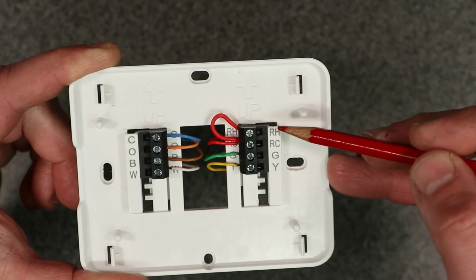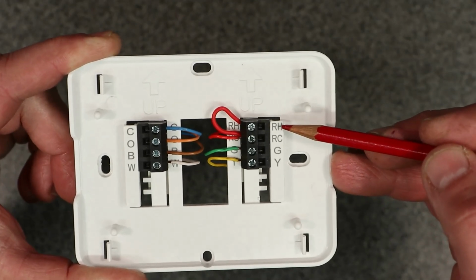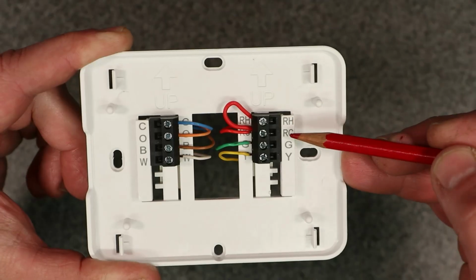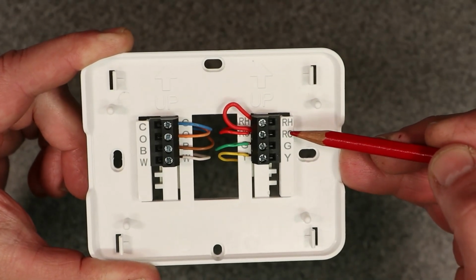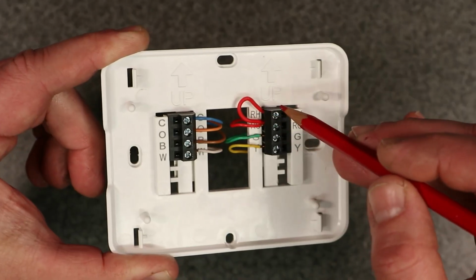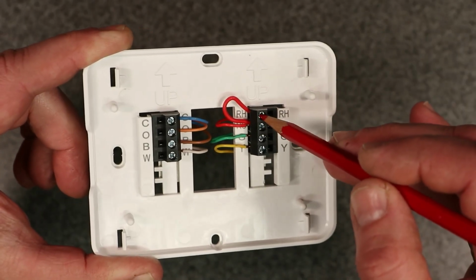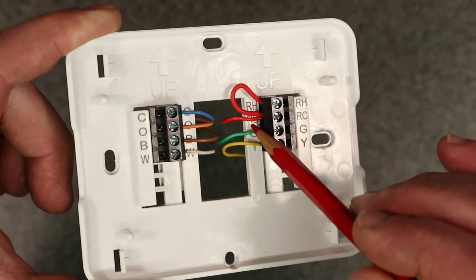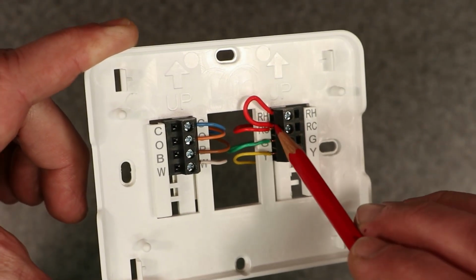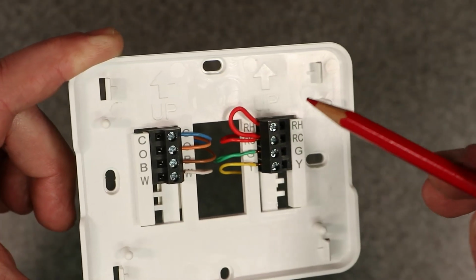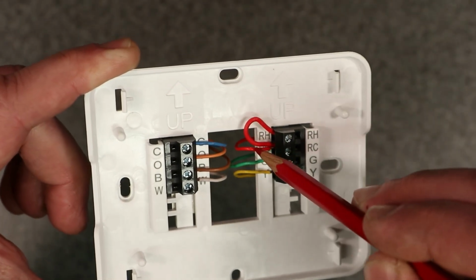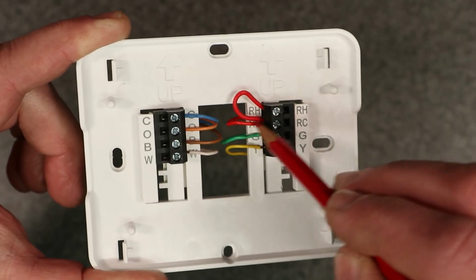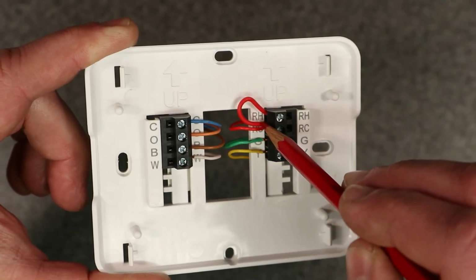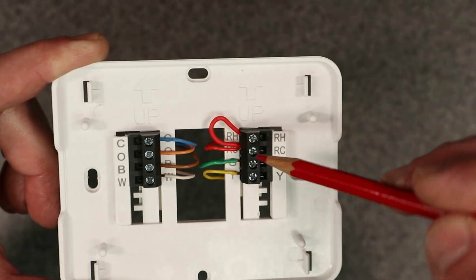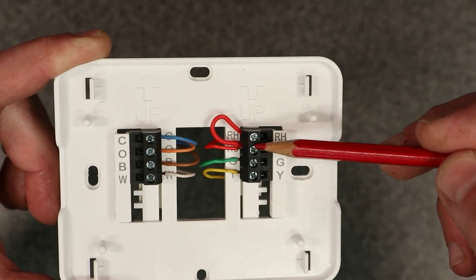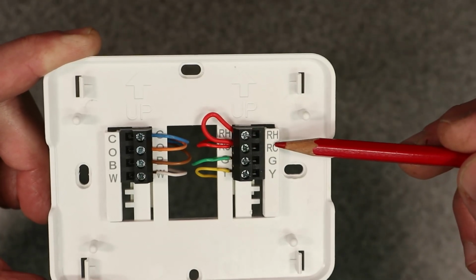Moving along to this side here, we have the RH. That's for your 24 volts power for your heating. RC is for your 24 volts power for cooling. Now, if you had 2 red wires, you would hook up one of the wires to each. But here, as you can see, we have a jumper. I have one single wire going to this terminal, and then it's jumping over to the RH. That's completely fine. This came with the jumper wire, and that's how you would hook that up if you only had one power wire, one 24 volt transformer wire. So they would power up both. It would bridge this gap. For both of these, it would power up and energize both terminals, okay?